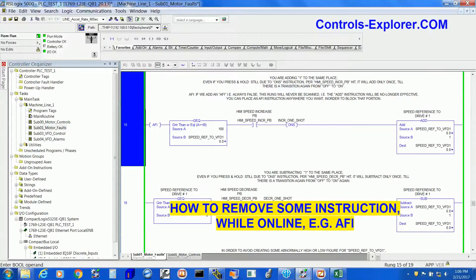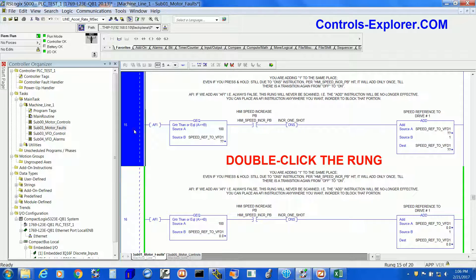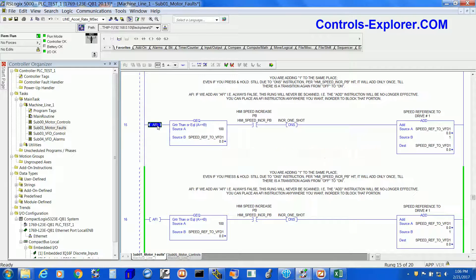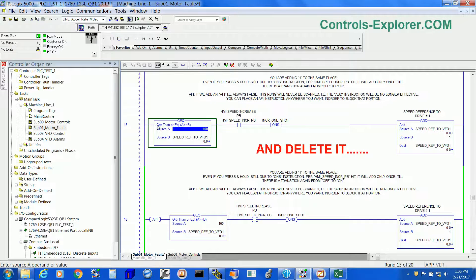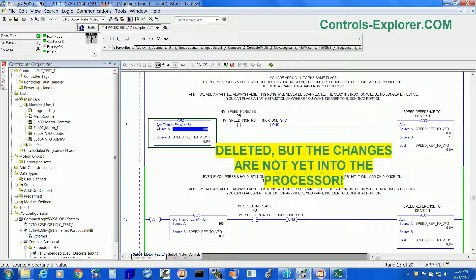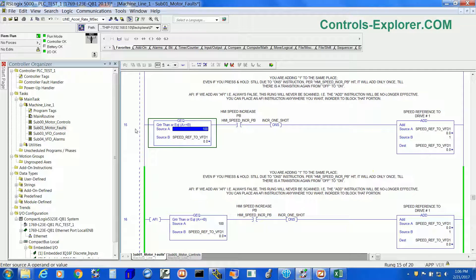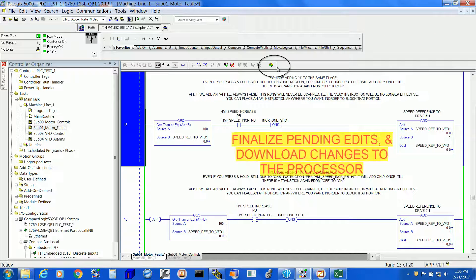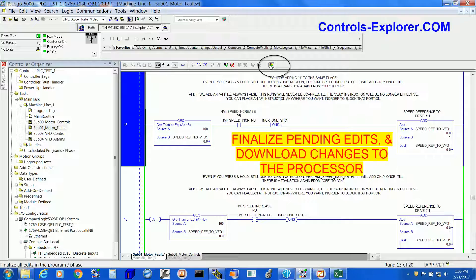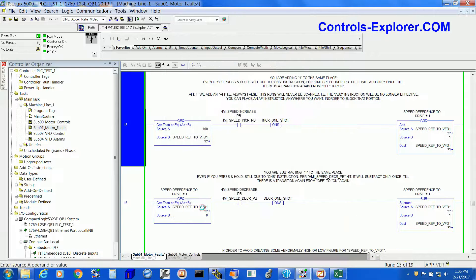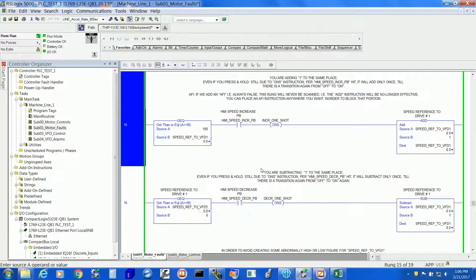Let's begin. Starting with something very simple — how do you remove an instruction? Select the rung, double click, we are going to remove the AFI, select it, and just delete it. Once you do the delete instruction, next you need to accept the pending edits and download. Select right over here and download it to the PLC, select yes. If there is no error, it will download — and we have downloaded it.